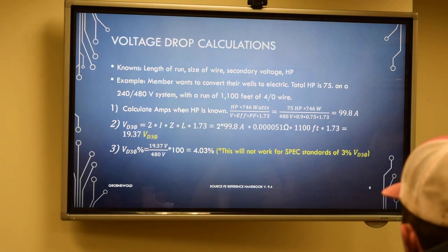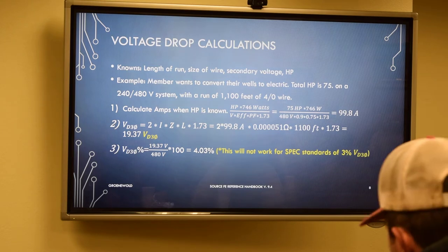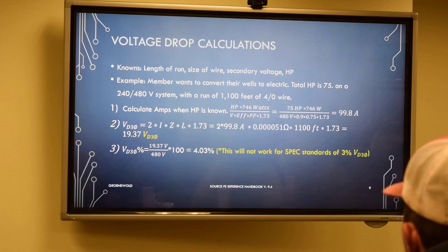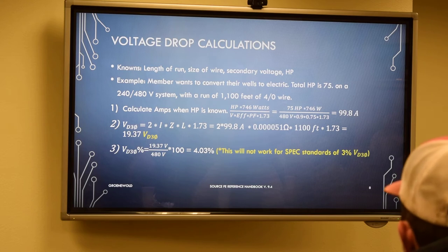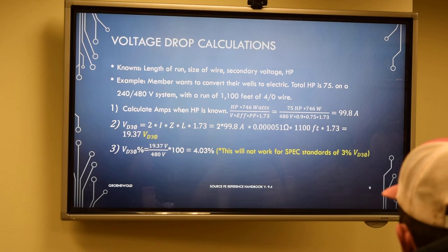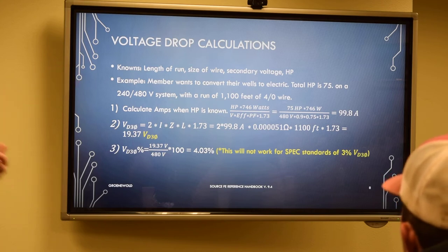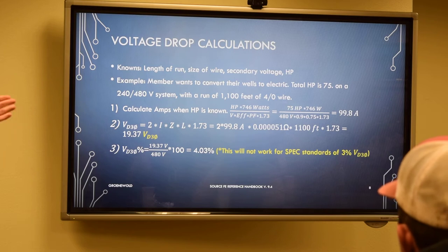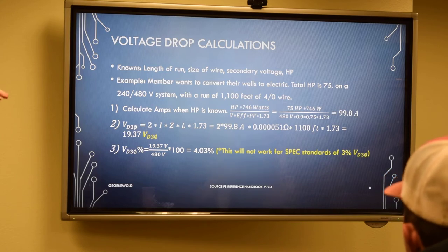Next example I'll go over is just going over how to calculate your voltage drop. Here's a basic voltage drop calculation where you know your length of run, the size of the wire, your secondary voltage, and a known horsepower. An example in your everyday use would be a member wants to convert their wells to electric, and the total horsepower that they have is 75 on a 240/480 volt system with a run of 1,100 feet of 4/0 wire. I've put this calculation right here, I know we have the calculators that do it, but if you want to see it, you take your 75 horsepower and multiply it by the 746 watts. And I have a slide further on that, why we use that number.